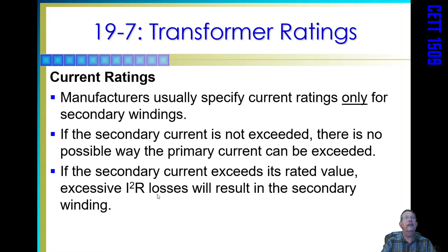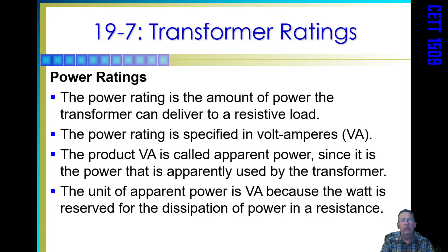So the power rating is the amount of power the transformer can deliver to a resistive load. The power rating is specified in volt amperes, or VA. The product VA is called apparent power since it's the power that is apparently used by the transformer. How about that? Apparently used by the transformer. The unit of apparent power is VA because the watt is reserved for the dissipation of power in resistance.